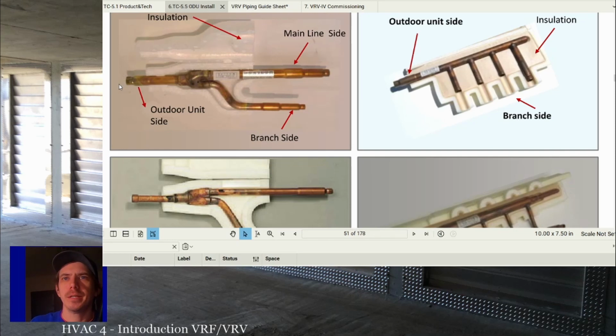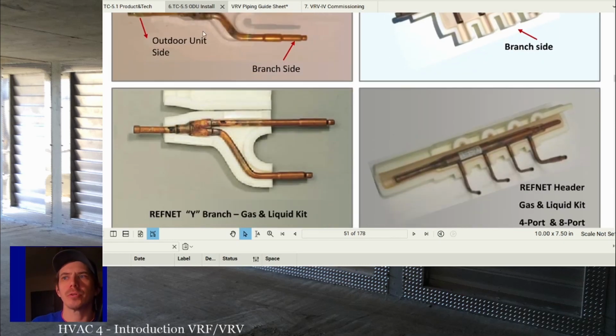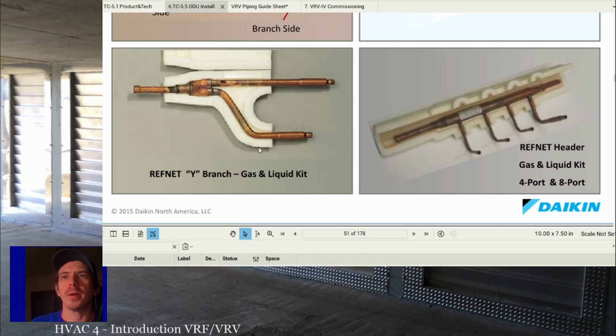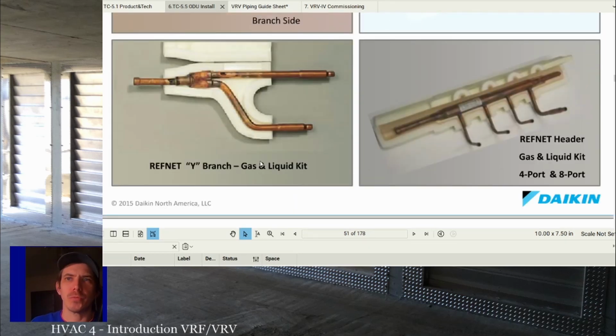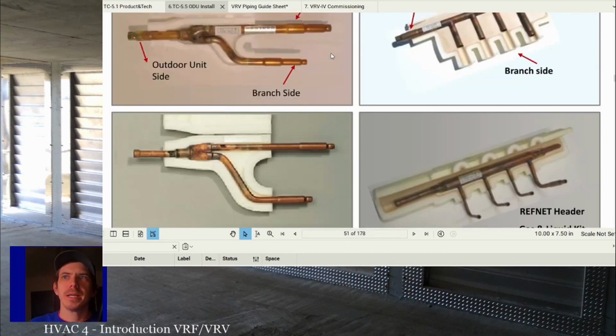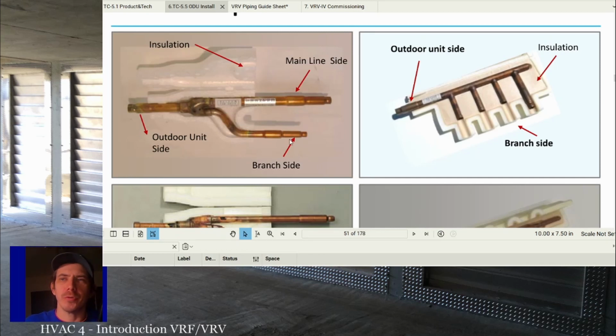But you'll see that you have this single pipe come in. So this is outdoor unit one. This is a regular RefNet Y branch. And they come in kits for your gas and liquid, or your gas, liquid and your high pressure, low pressure gas. So you'll have 3 Ys in one box. And a lot of times it'll come with a bunch of reducers and stuff too. And you can see looking at this that you have a small connection and then it gets bigger and then it gets smaller again, right? And it comes into this little fitting right here that they braze these other sections to. And then it's this size, then it gets bigger, then it gets smaller and smaller. And it does the same here. It comes in, gets bigger, then gets smaller and smaller.